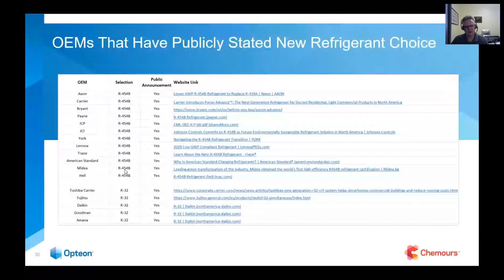But when we look at it, these decisions were really made by the manufacturers. And it's really hard to say, time will tell, but I think it might be 60% or 70% of the manufacturers going 454B, and 30 to 40% of the manufacturers moving to 32. So it's hard to say, but time will tell where that ends up. But certainly both refrigerants are going to be commonplace as alternatives to 410A in residential and commercial.